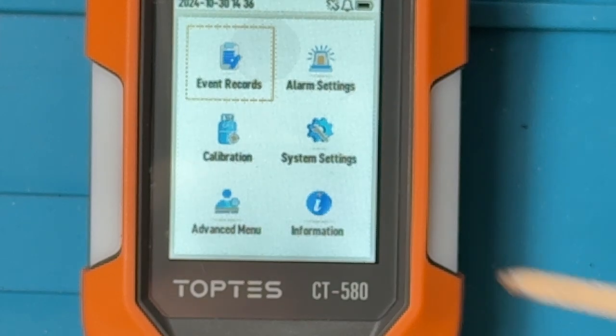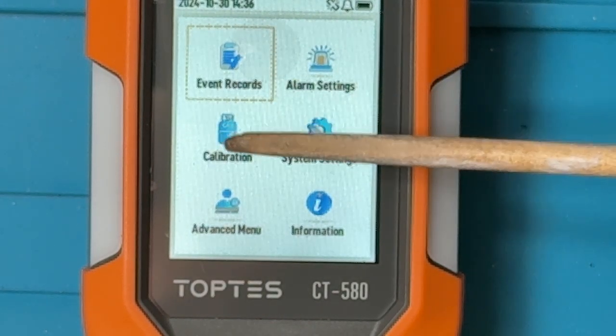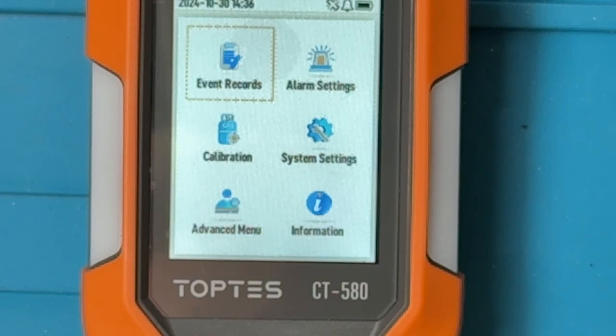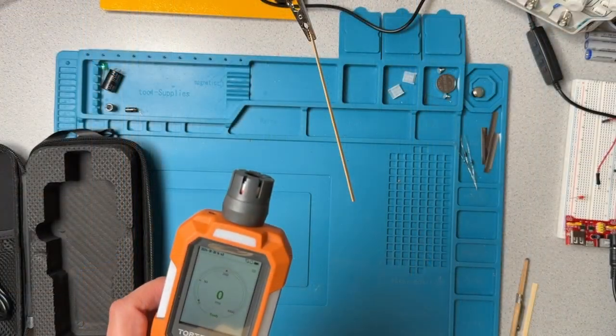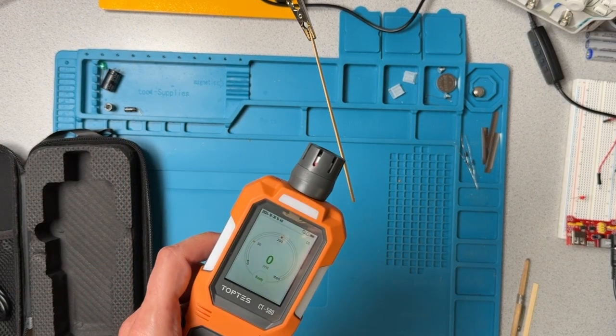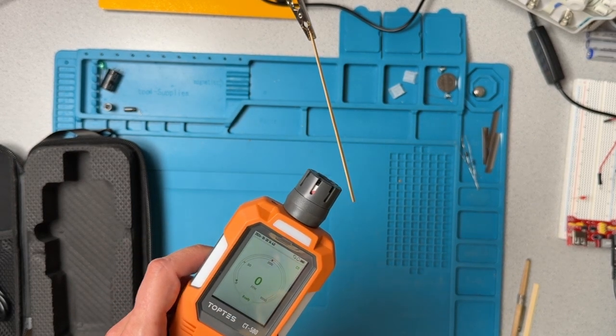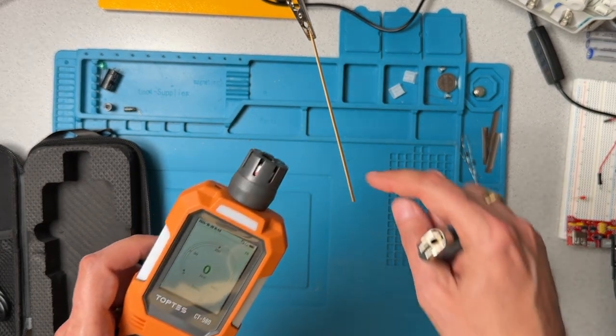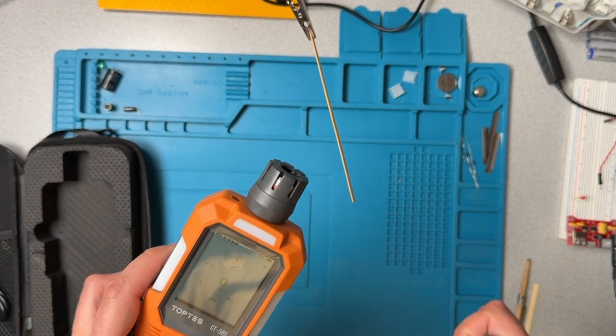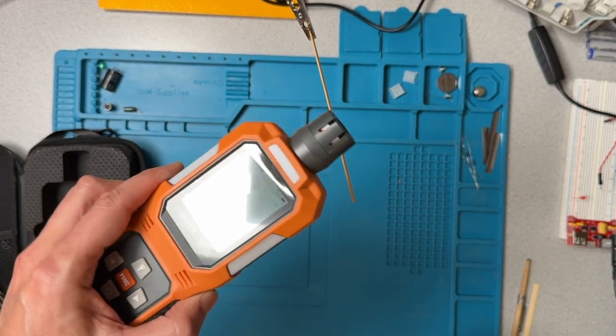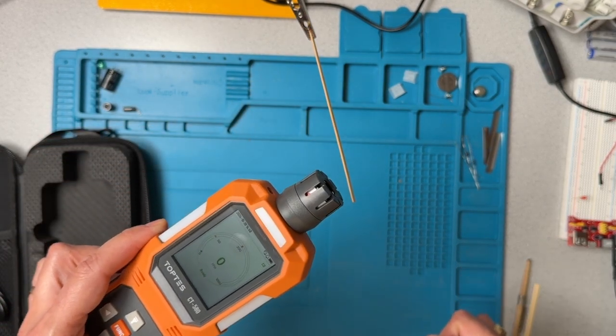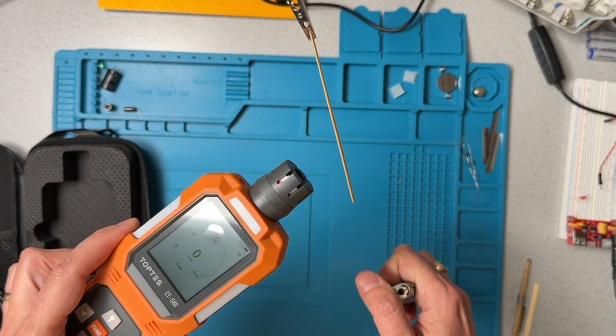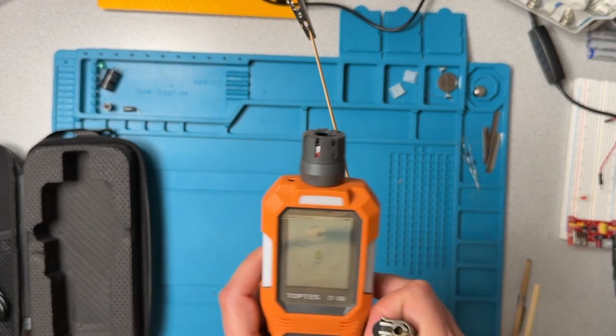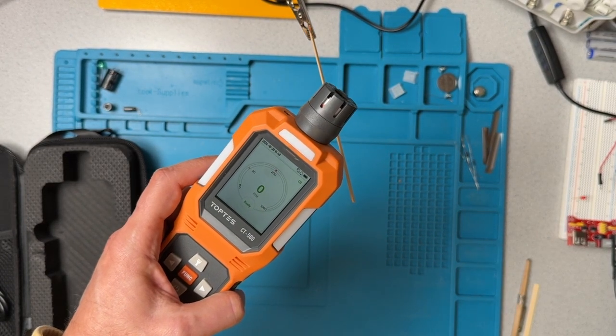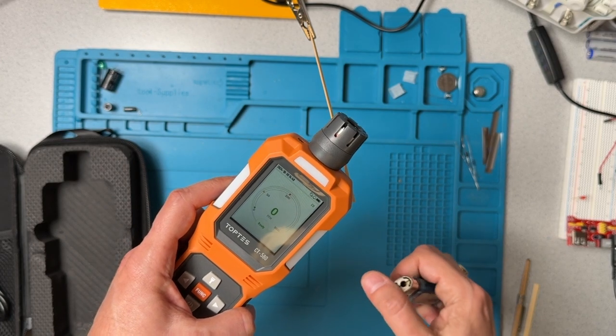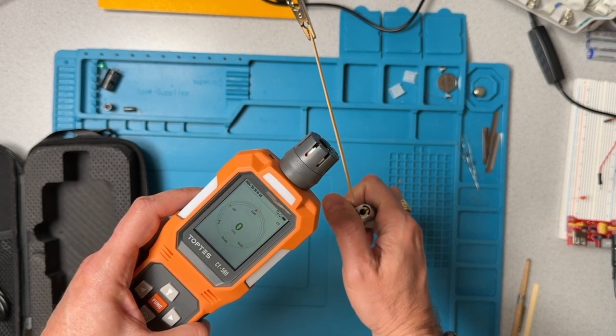So I think now we've gone through event records, alarm settings, calibration, system settings, advanced menu information. Yep, we've gone through all of those. Now I'm going to try to generate a little bit of carbon monoxide to see if we can get the alarm to trigger. What I'm going to do is I have a little piece of wood here. I'm going to set the piece of wood on fire, and we'll see if we can find a place where there's some carbon monoxide being produced by the wood as it burns, and hopefully we'll be able to see the display on the detector as well. We'll try to keep everything in the frame.